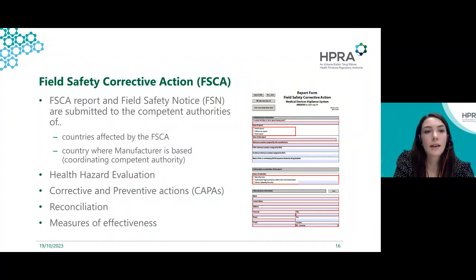In communicating the field safety corrective action, the MDR requires that the FSCA report and the FSN are submitted to competent authorities of countries where the affected products have been sold, and also the country where the manufacturer's authorized rep or manufacturer is located. There's also an approved template form for submitting details of an FSCA. This is seen here on the right. Besides the FSN and the Field Safety Corrective Action Report, there are other background documents that will be needed to support the decision.